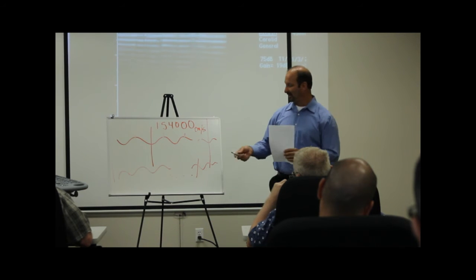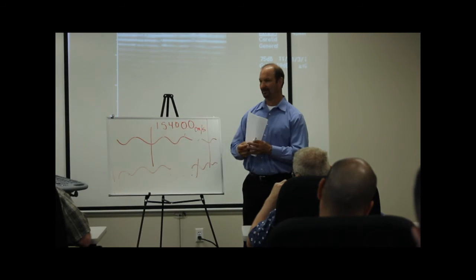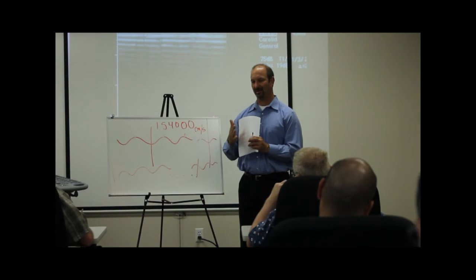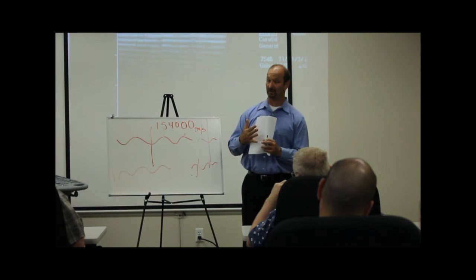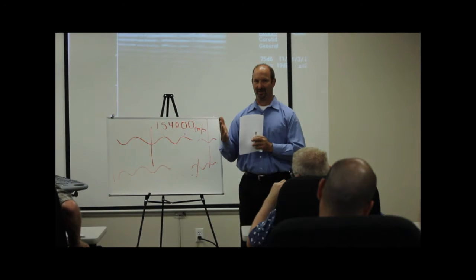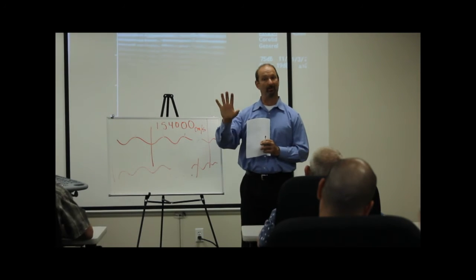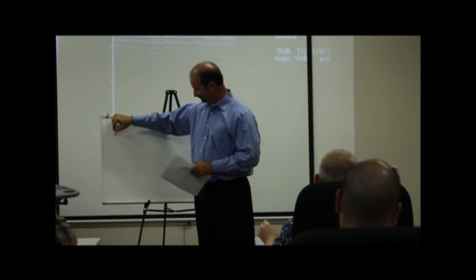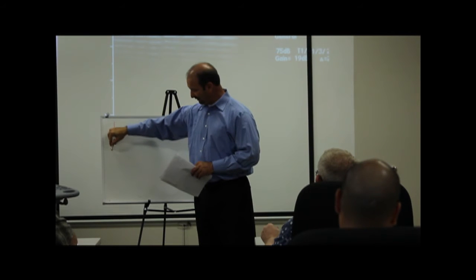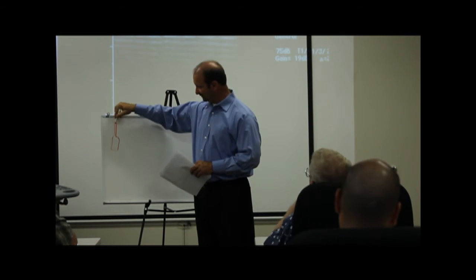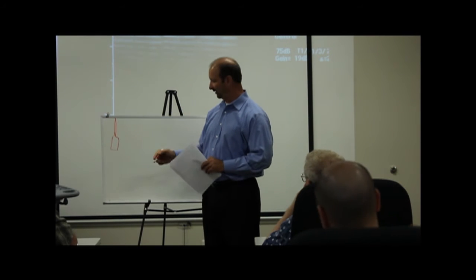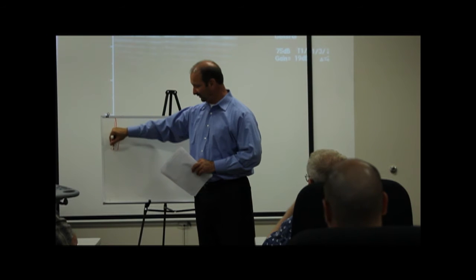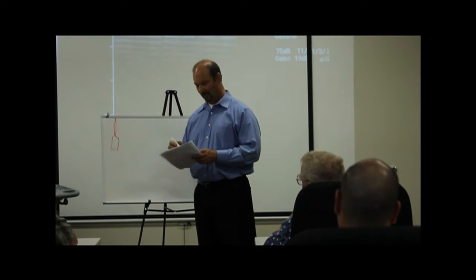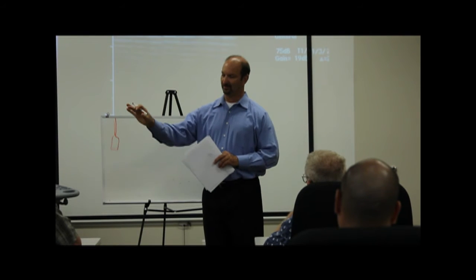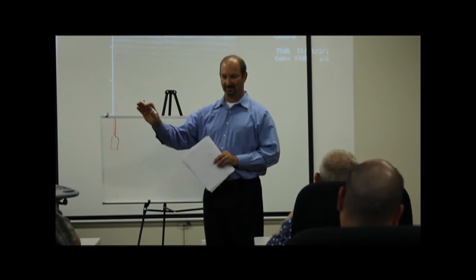So for the frame rates, it may do 500 of these pulse-listen cycles and take out all that information. The information that showed up more times than it didn't, it makes that one frame. It takes 24 of those frames, and that's your frame rate. For the most part, all transducers that provide an image today are pulse wave. They'll have 96 little elements in the end, and those elements, like I said, will excite, send out noise, stop, and listen back.